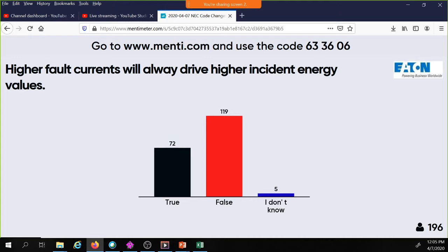But in any case, the reason I say higher fault currents do not always produce higher incident energy is because when you increase your fault currents, you're going to be moving into faster clearing times of the overcurrent protective device. We're going to be talking about 240.67 and 240.87, which is all about arc energy reduction. And there are two fundamental principles you have to understand with regard to the overcurrent devices, because overcurrent devices are going to be those things that reduce your incident energy. And it's higher currents that will get you faster clearing times.